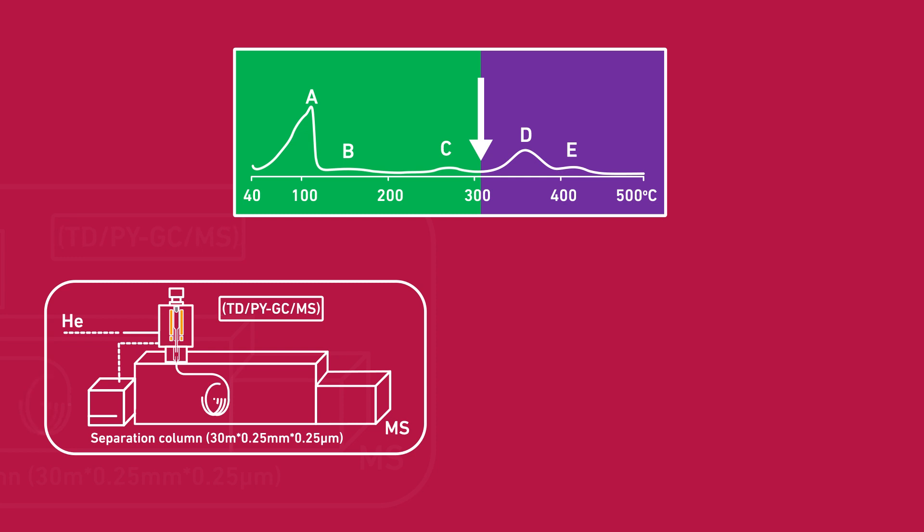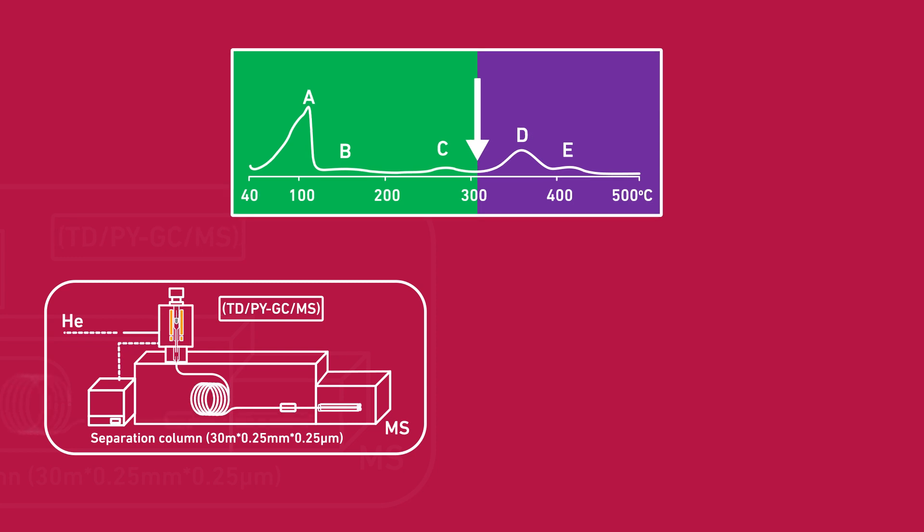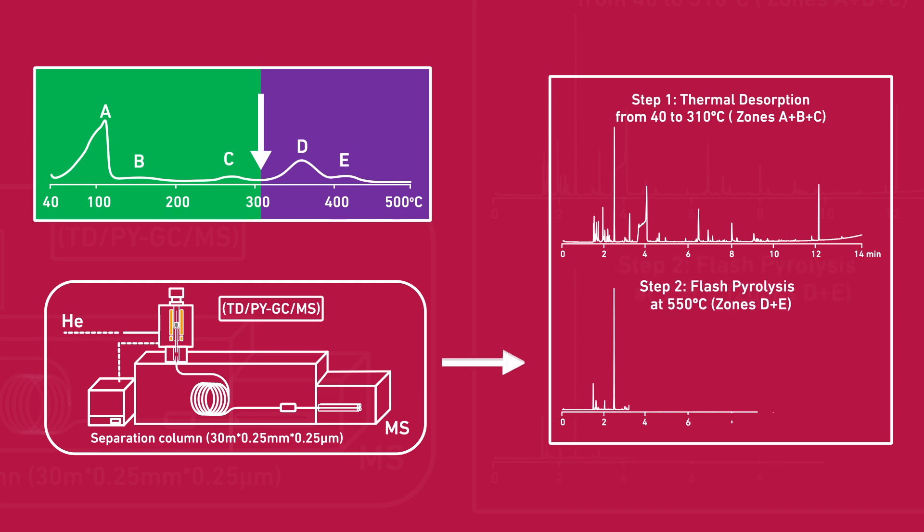The pyrolyzates are transported directly to the analytical column, and the pyrogram is generated. By using the double-shot mode, first, volatiles evolving from the sample are analyzed by thermal desorption. Then, the residual sample is pyrolyzed for identification of the heavier and polymeric content of the sample.